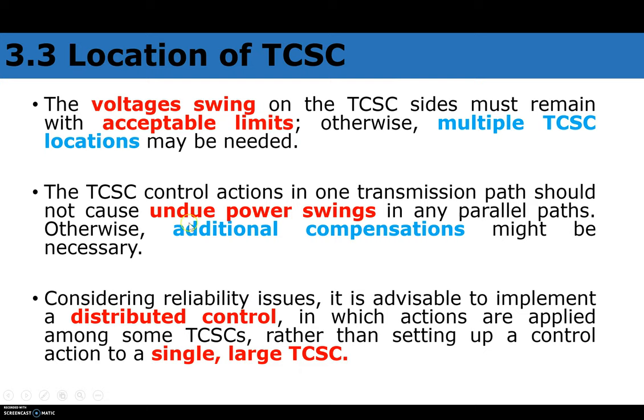TCSC control actions in one transmission path should not cause undue power swings in any parallel paths. Control actions must not cause additional power swings; otherwise, additional compensators might be necessary. Only one TCSC at one location is not a wise idea. We have to consider additional compensators at multiple locations. Considering reliability, it is advisable to implement distributed control so that actions are coordinated among all TCSC units rather than relying on a single large TCSC.